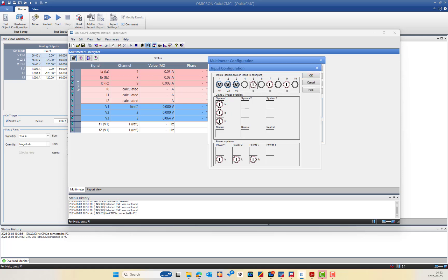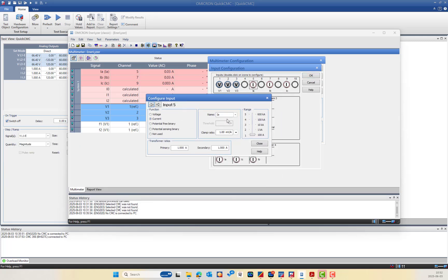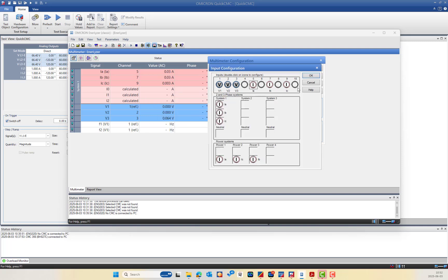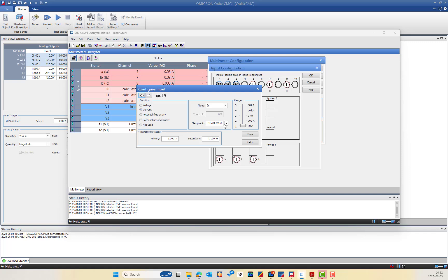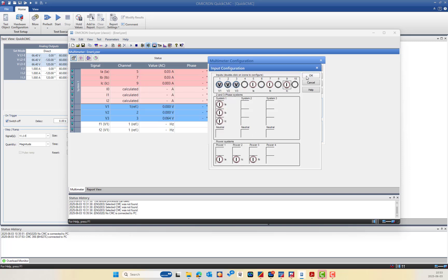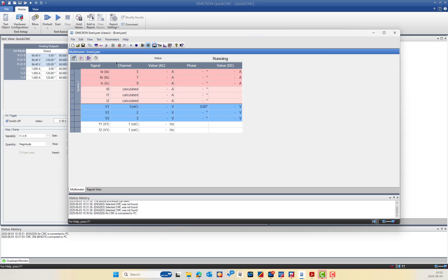The same applies for V2 and V3. For IA on input 5, double-clicking shows the configuration to measure current, renamed IA in the hardware configuration, with a clamp ratio of 1 millivolt per ampere and a range of 100A. For IC, the clamp ratio is 10 millivolts per ampere because the shunt resistor is 10 milli-ohm, giving a smallest range of 10A.